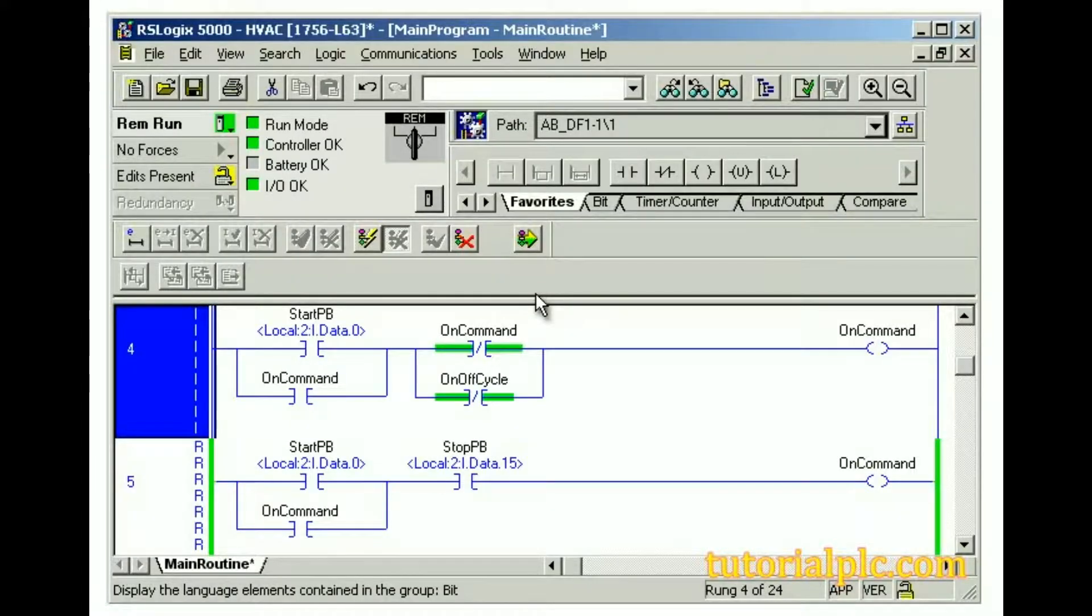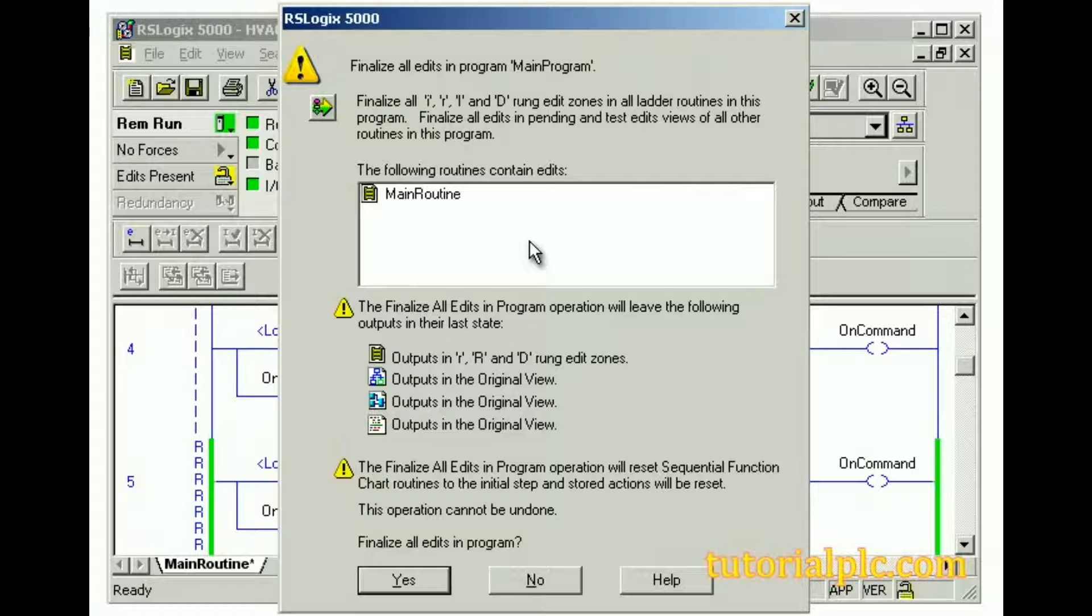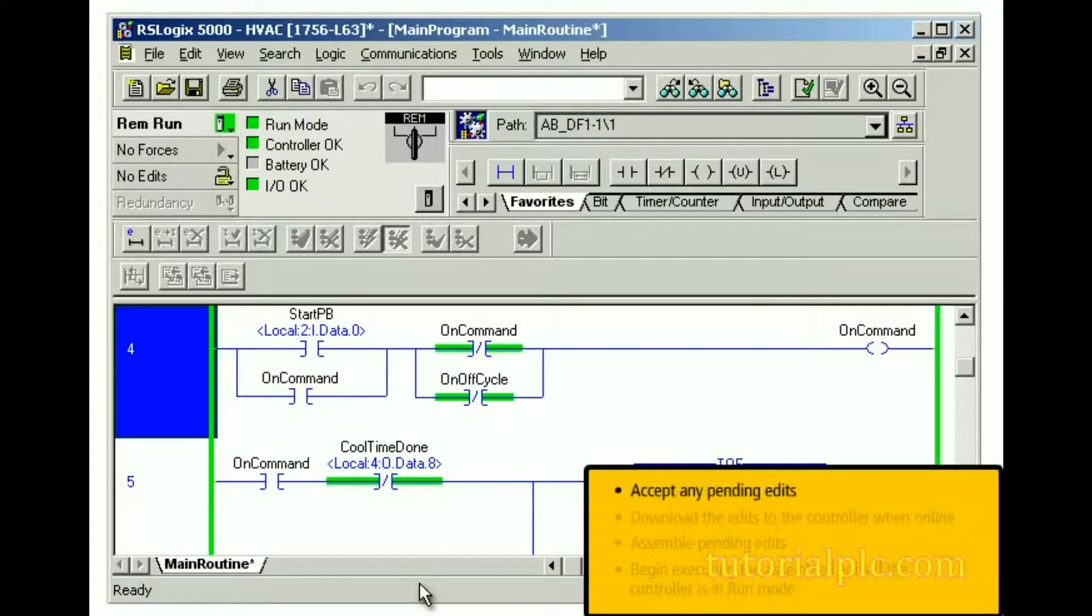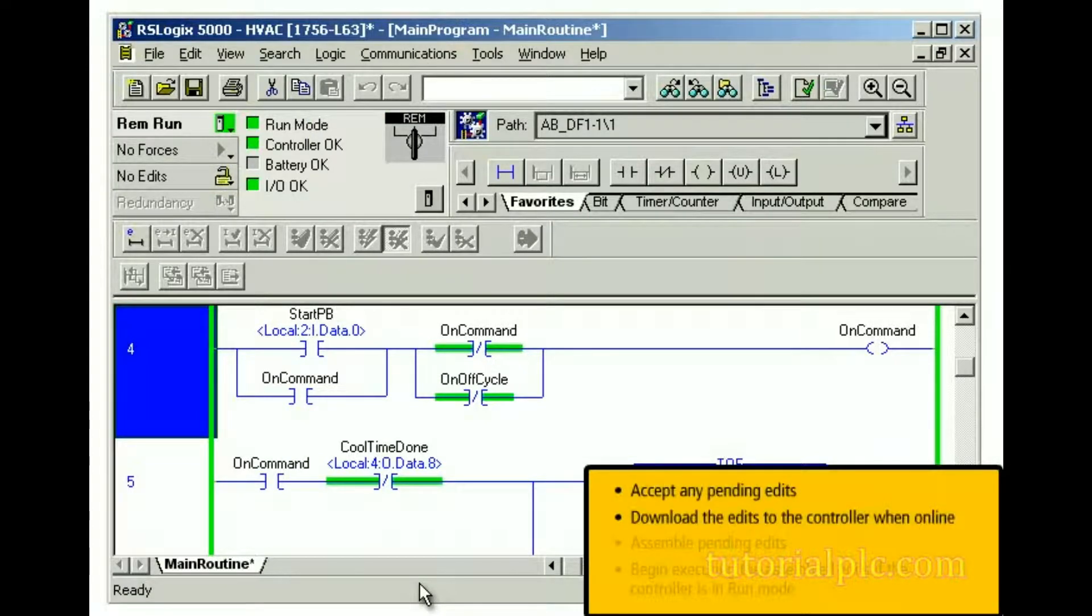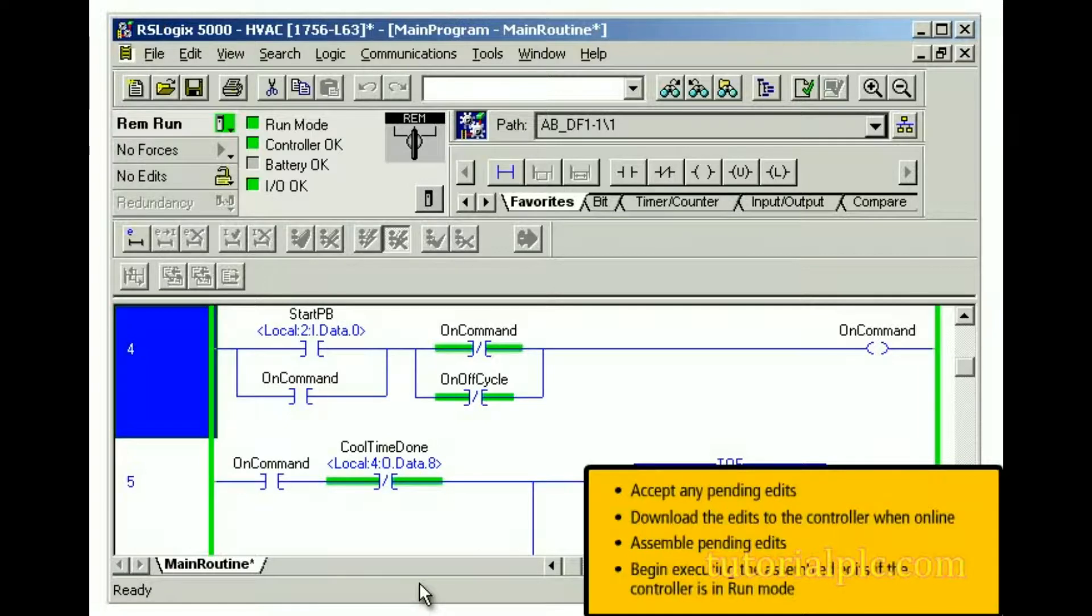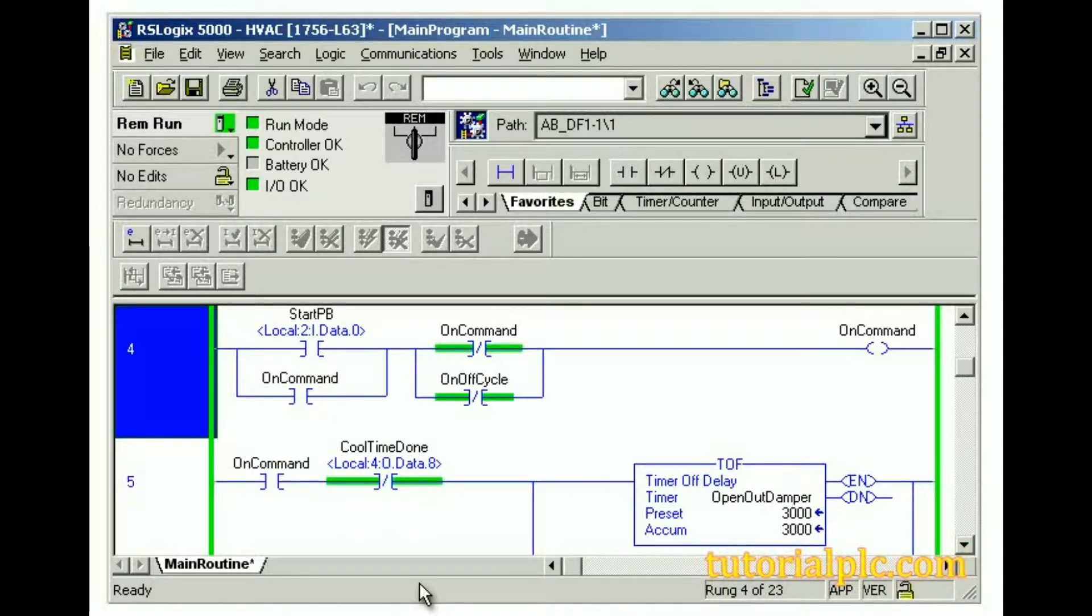When you click the Finalize All Edits in the Program button, a dialog box is displayed that prompts you to confirm whether you want to finalize all edits. When you click the Yes button, RSLogix 5000 software will accept any pending edits, download the edits to the controller when online, assemble pending edits, and begin executing the assembled edits if the controller is in Run mode. If a verification error occurs in any pending edit zones, none of the pending edits will be committed to the controller, and the finalize process will stop.